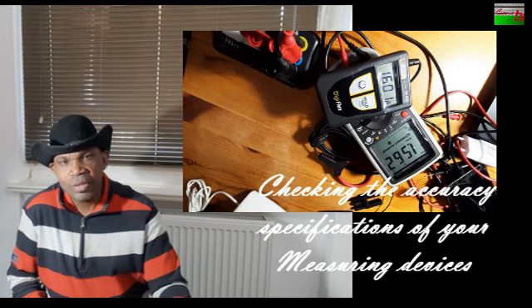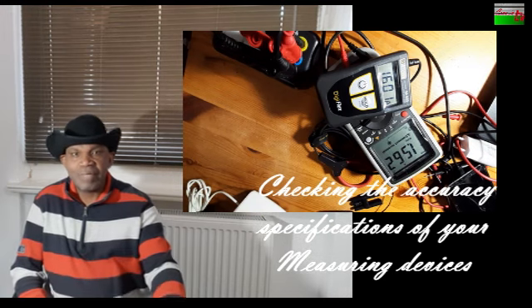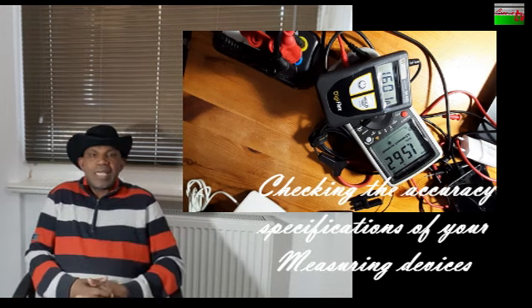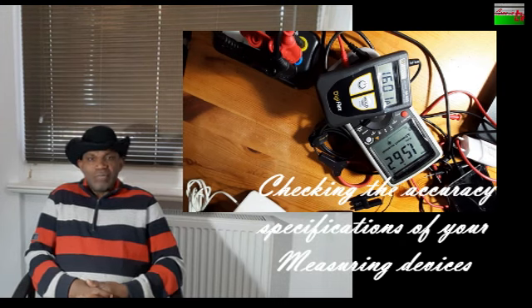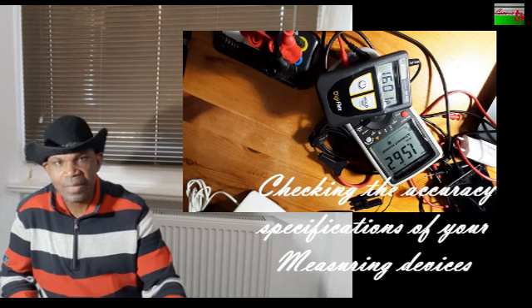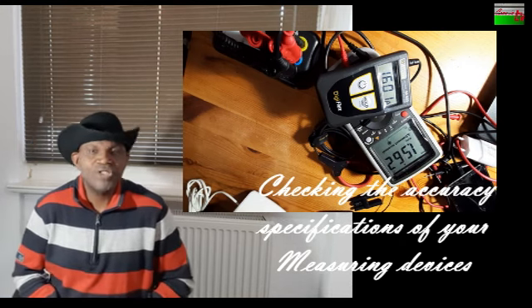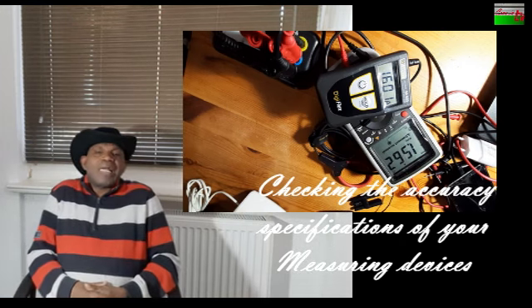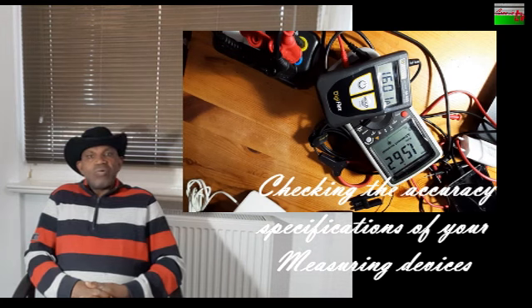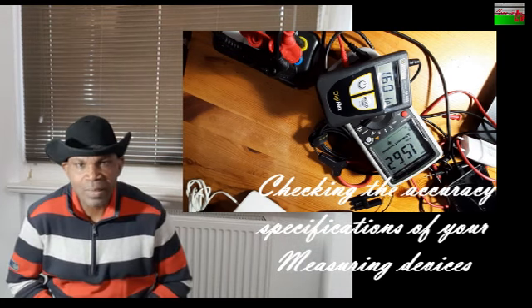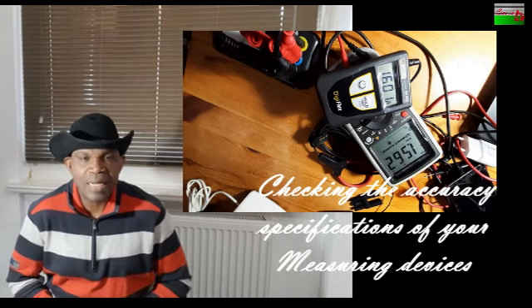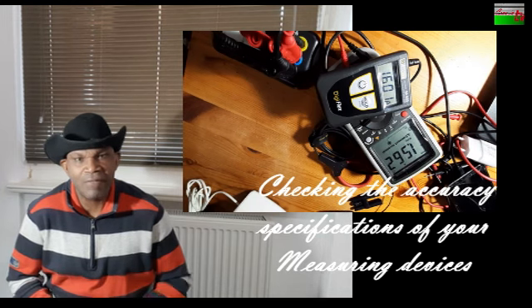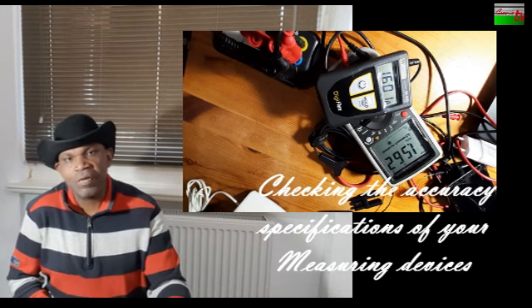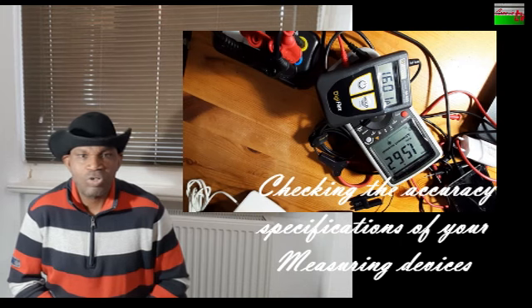During a laboratory experiment or testing for average values of output, current, power, etc, if you take your measurements from one measuring device always, there are two possible ways you can verify if your measurements are correct. The first is bringing your measuring tool to an equipment calibration center, where it can be tested using the standard SI system to verify accuracy. This costs you a lot of money.